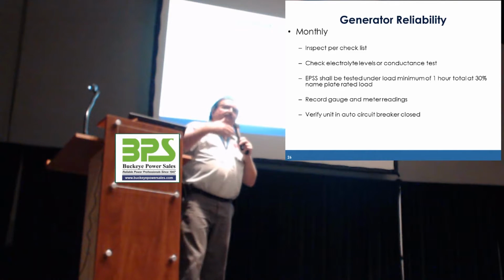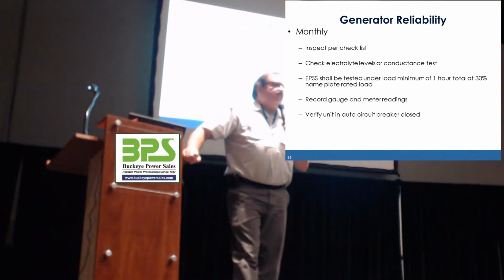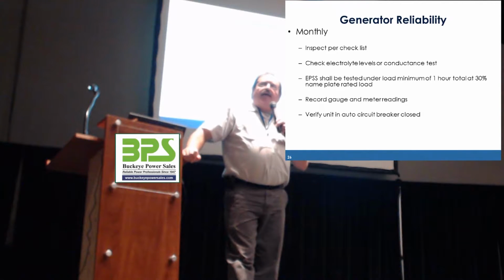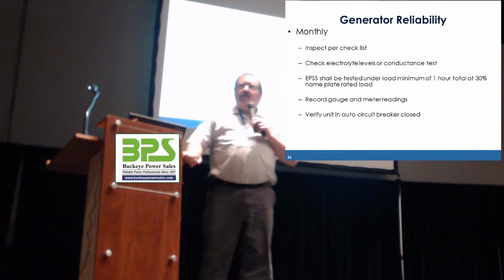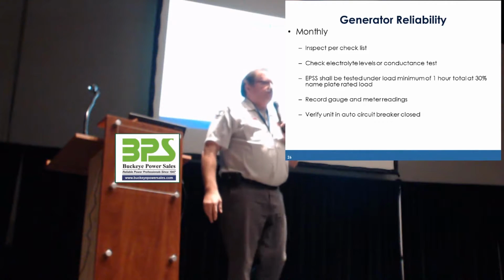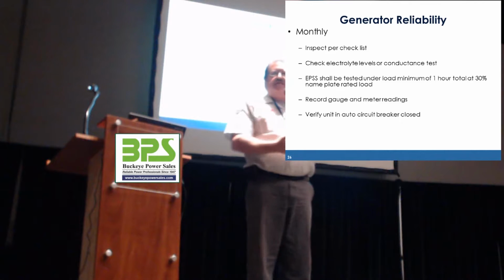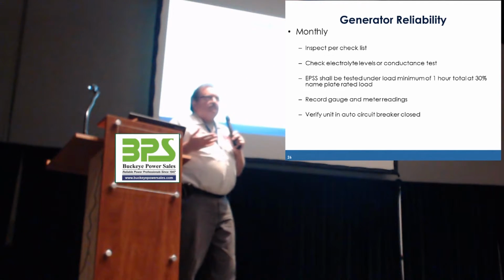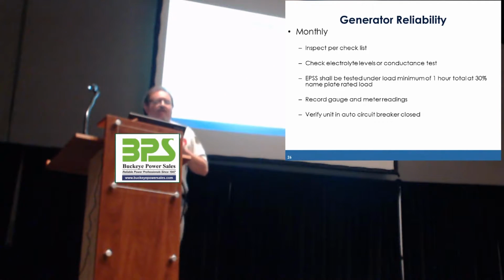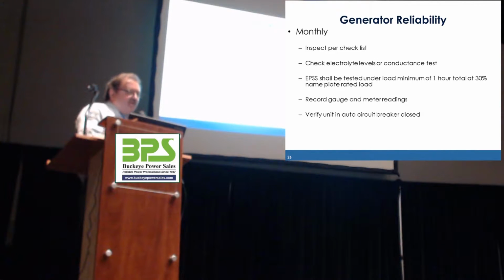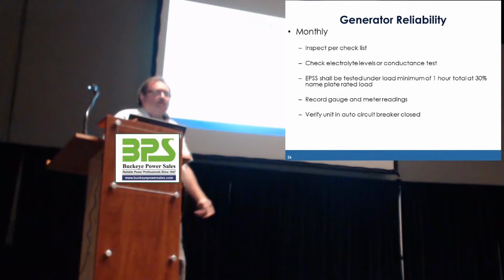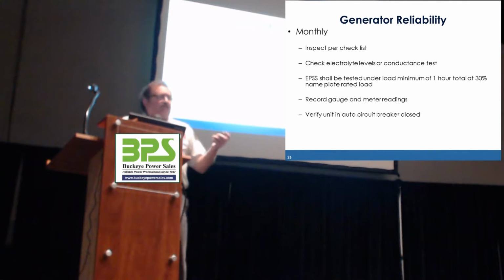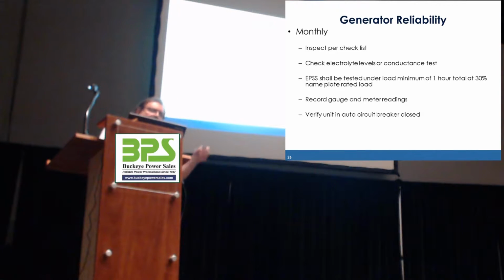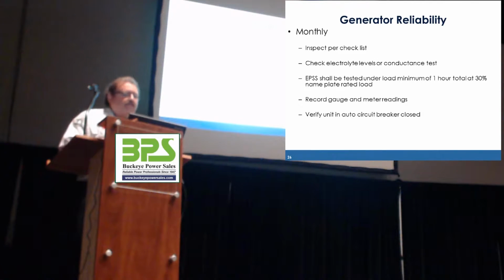We had a representative out from the breaker manufacturer, who told them the same thing. They won't do it. And for whatever reason, they're so hard-headed now, they're just going to kick the can down the road another 5 years. They want to replace the whole transfer switch because they have no confidence in this switch. Well, they're going to have the same problem in 5 years if they don't actually transfer that switch. Again, we have to record the gauge and meter readings and verify, the last thing when you're done, if you've manually operated anything, that the controls are in automatic and the breaker's closed.